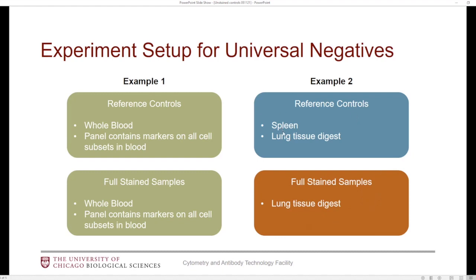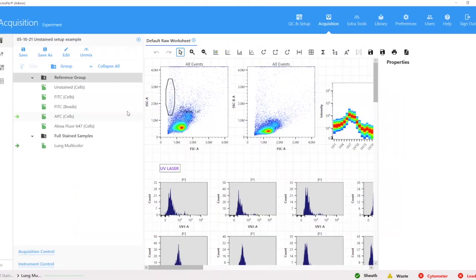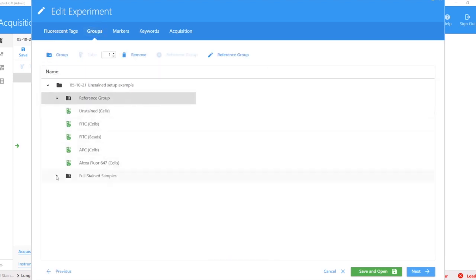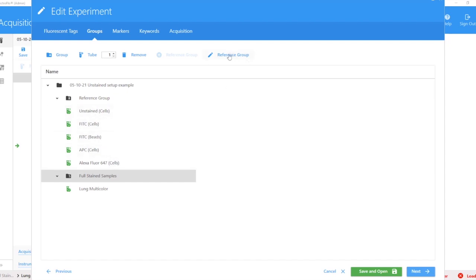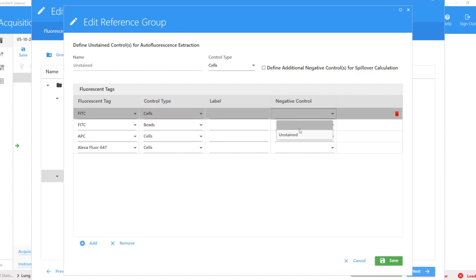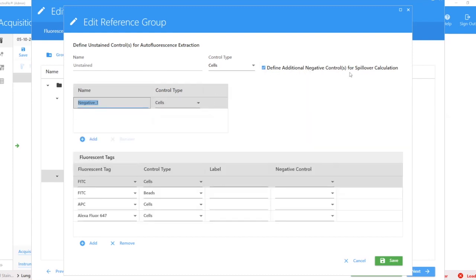You have lung tissue digest for your fully stained samples and you want to utilize the universal negatives — sometimes you need the universal negative from your spleen tissue and sometimes from your lung tissue. In SpectroFlo, this is going to be underneath the modify experiment or edit button. Then we go to the groups tab and can see all of our tubes. In order to edit the reference group, we modify it with the button up here. The universal negatives are basically the last column, which is called negative control.